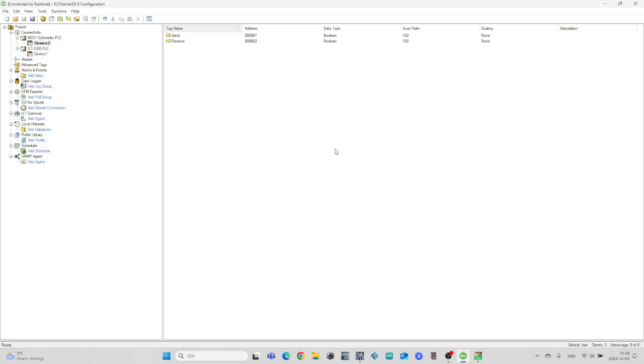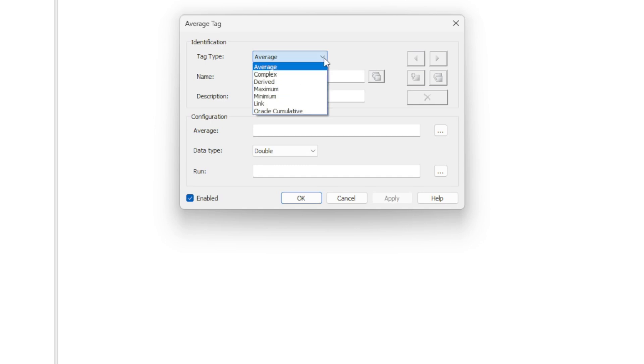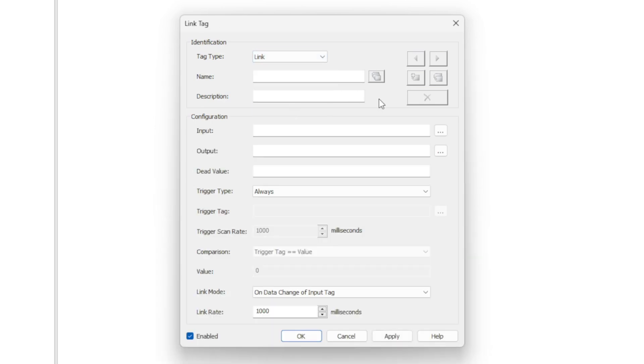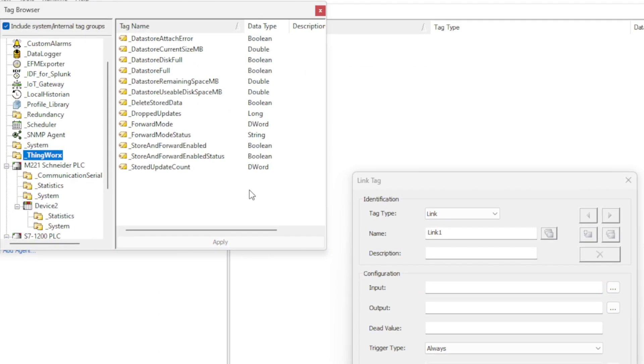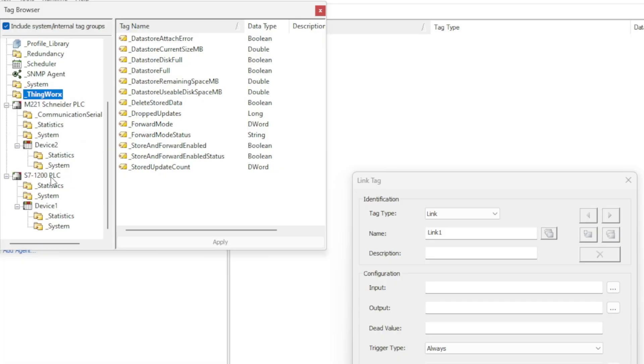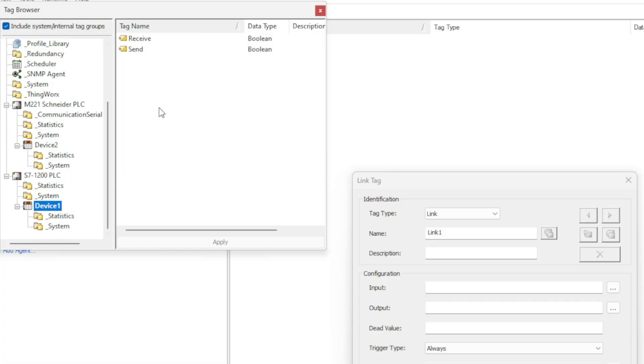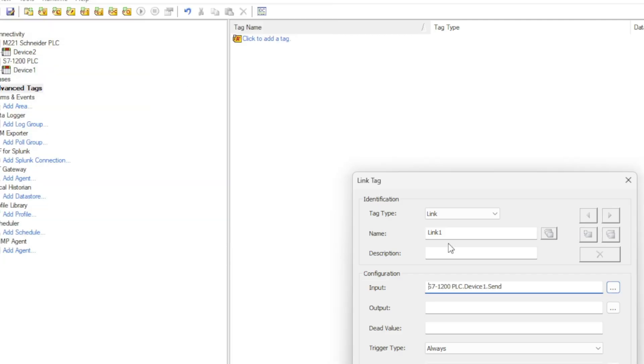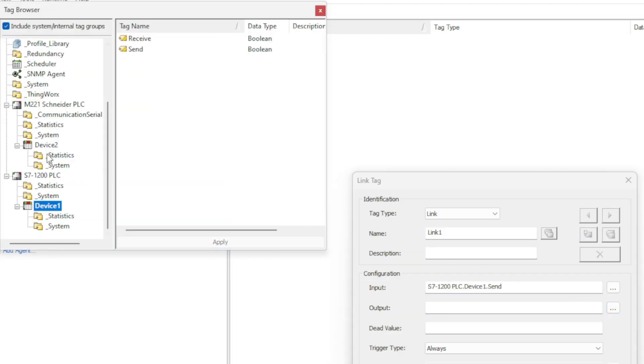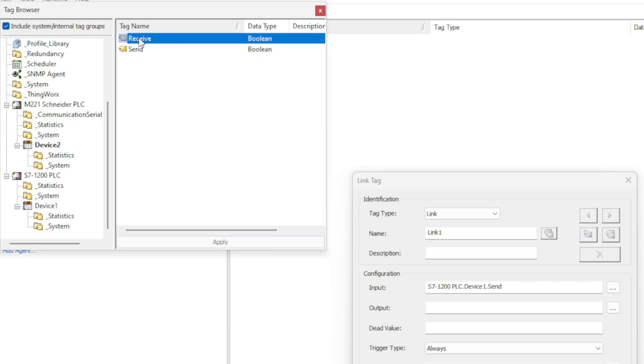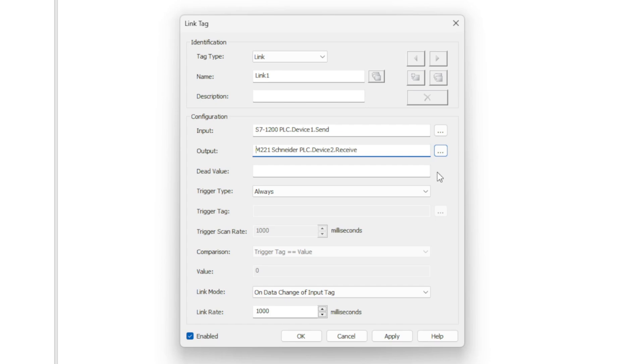Now to link the tags together we want to click on advanced tags. Then we add a new tag and choose the tag type as linked tag. On the input side I will choose the send tag from the Siemens PLC, and on the output side I will choose the receive tag from the Schneider PLC. That's basically all we need to do — I will do the same with the other two tags.